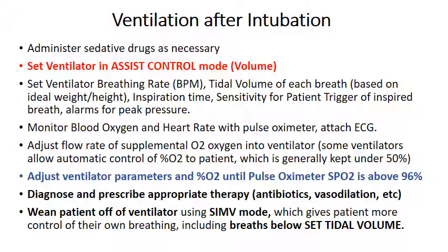So the ventilator breathing rate is set. The tidal volume, which is the amount of air that goes into each breath, is set based on the ideal weight-height ratio of the patient. Inspiration time is set, and sensitivity for patient trigger of inspired breath is also set, as well as alarms for peak pressure.